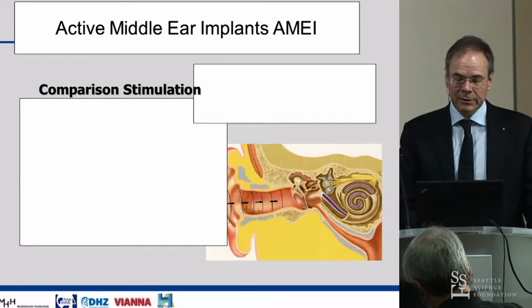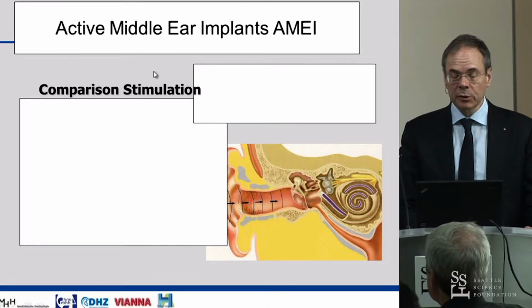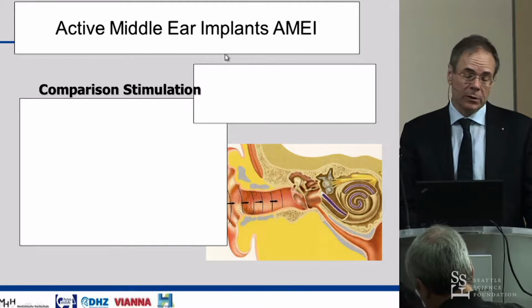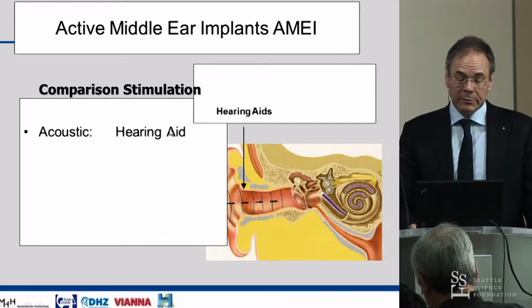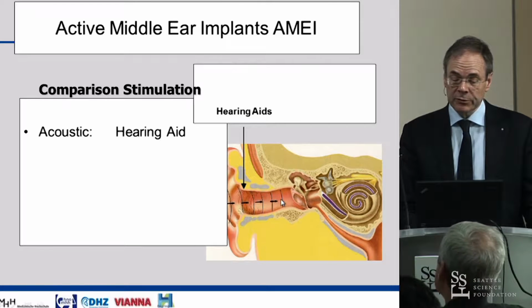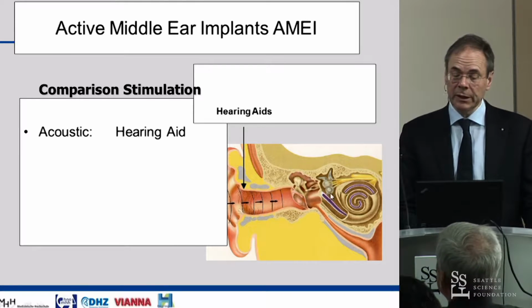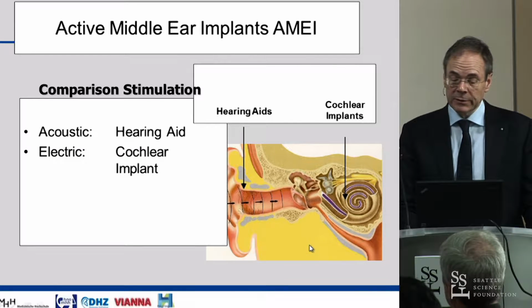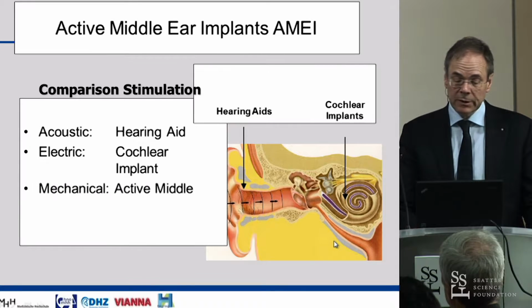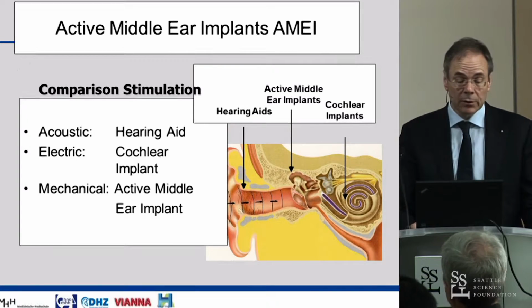Now let's go beyond that, and that's the field where you go closer to the inner ear with your vibratory stimulator. We call them active middle ear implants or acoustic implants, whatever. Just for the explanation, acoustic amplification is a hearing aid. It amplifies sound and basically delivers it through the outer ear canal. It has to go all the way through the middle ear into the inner ear. The cochlear implant stimulates the nerve directly, electrically, and replaces the hair cells. And in between, there are the mechanical stimulating systems, which stimulate mechanically somewhere on the ossicles or at the interface to the inner ear, and that's what we call active middle ear implants.